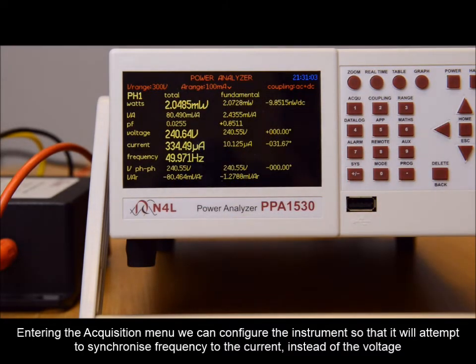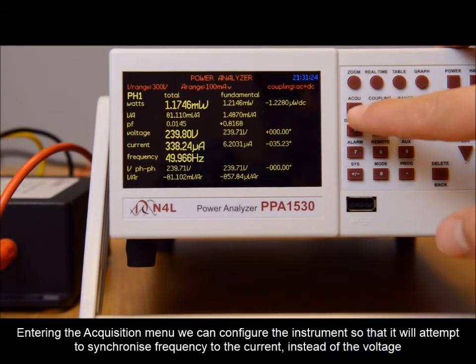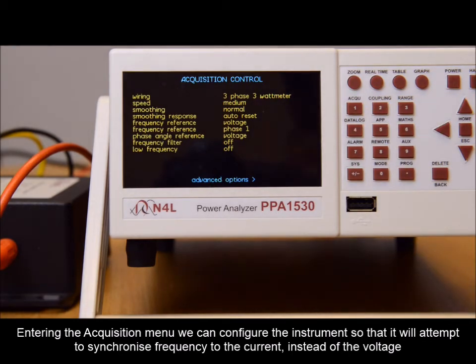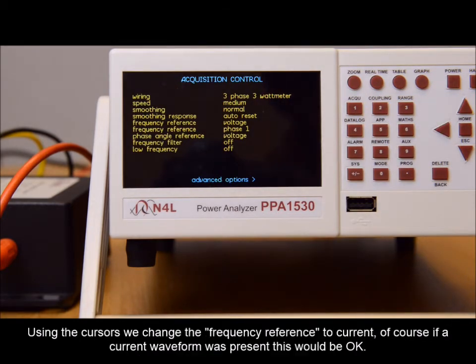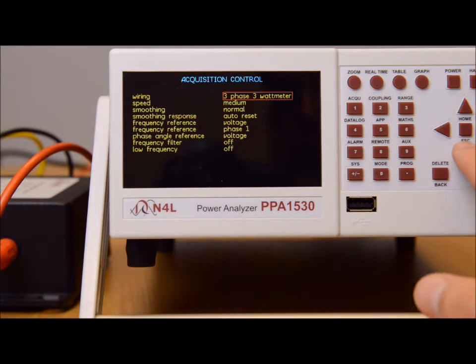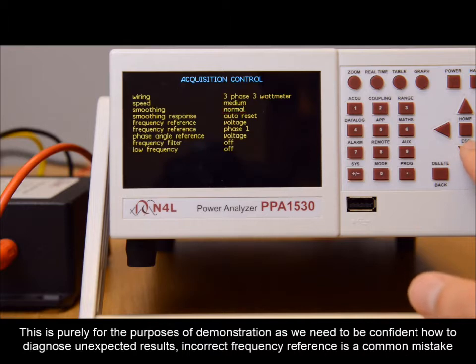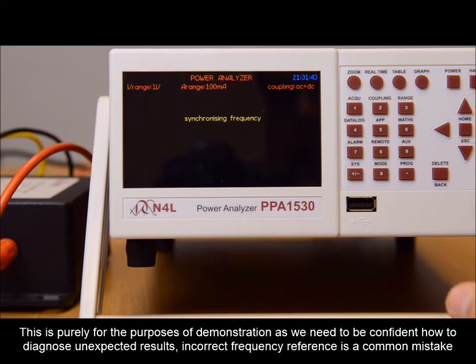Entering the acquisition menu, we can configure the instrument so that it will attempt to synchronize frequency to the current instead of the voltage. Using the cursors, we change the frequency reference to current. Of course, if a current waveform were present, this would be okay. This is purely for the purposes of demonstration, as we need to be confident how to diagnose unexpected results. Incorrect frequency reference is a common mistake.